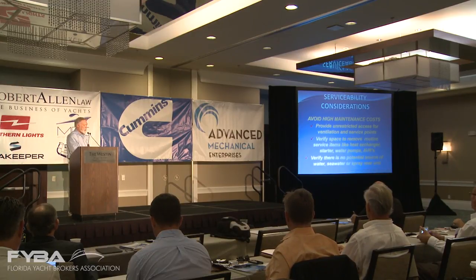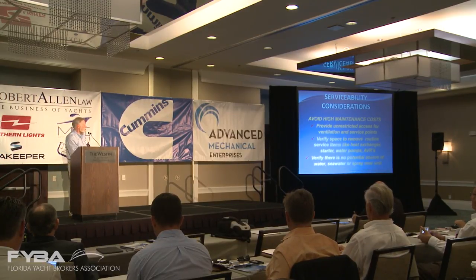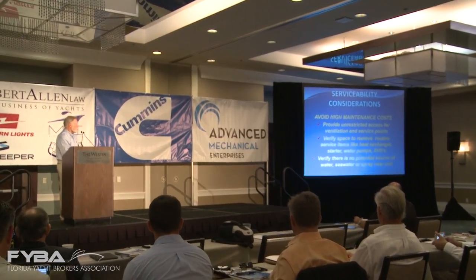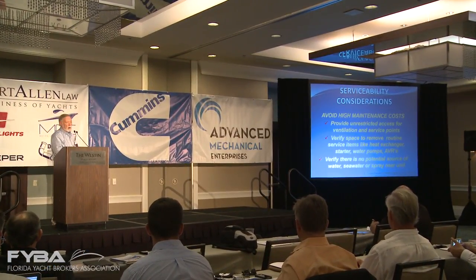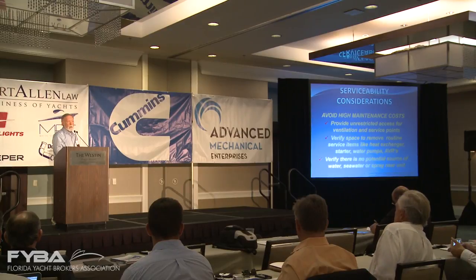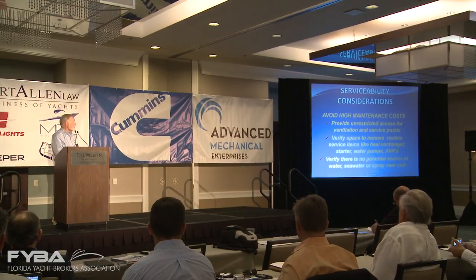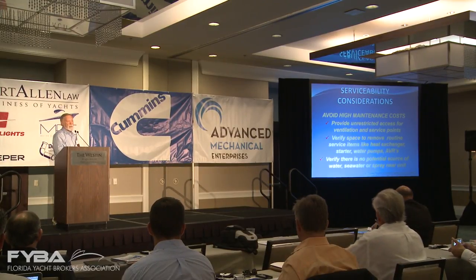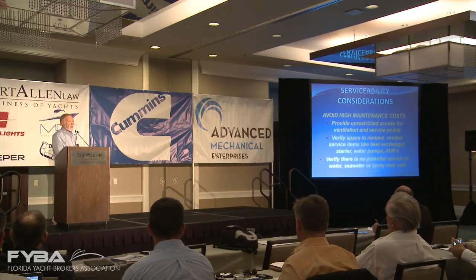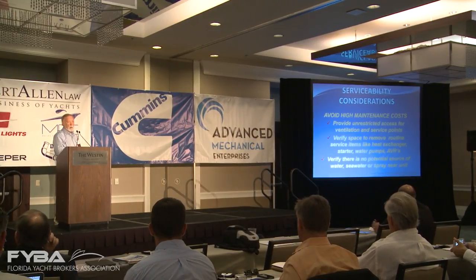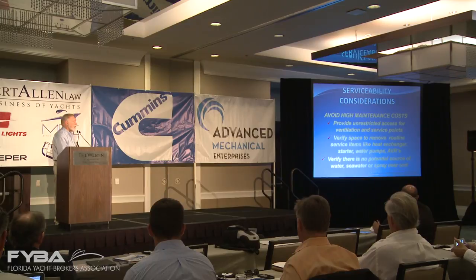Make sure there's enough serviceability space, particularly for heat exchanger service. The starter is typically on the non-service side, so it'd be nice if you didn't have to physically remove the generator from its mounts in order to change the starter. So it's a good idea to plan that much room.